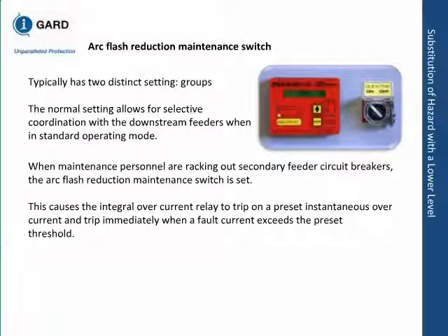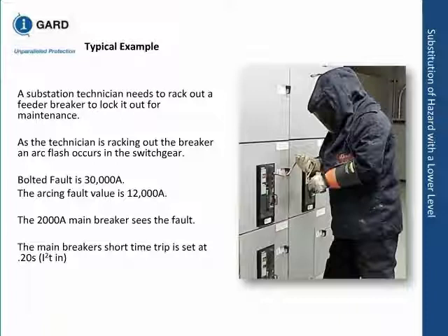Just to give you an example, how does it work? A person is going to work on a breaker, racking in and racking out. He or she is very close to the breaker, and just for discussion's sake, for this calculation, the fault current was 30,000 amps. Arcing fault value is 12,000 amps. Now in industry, 30,000 amps is not considered very high current. Some of our switchgear is rated for 85,000 or even 100,000 amps. It has a 2,000 amp main breaker.